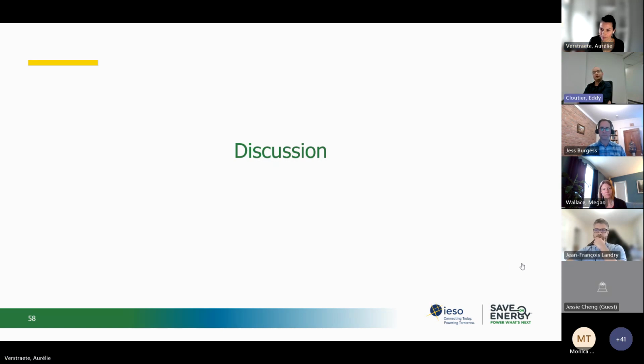Yeah, I agree with Aurélie, because if I might add, a lot of times what is shown on the BAS is not the reality of the system that you have physically in the mechanical room. So the first thing you want to do is make sure that you understand really how the systems are configured. It can be a heating system, a cooling system, a ventilation system. Unfortunately, what is shown on the control graphic is, I don't know, maybe 40% of the time not exact. So you need to understand the reality in the mechanical room.